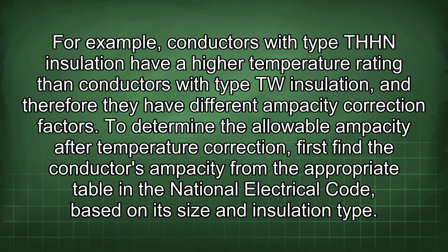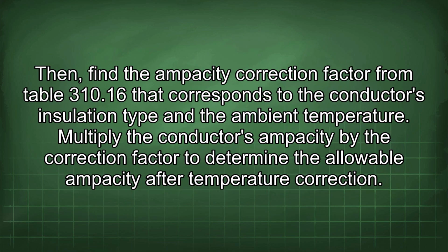To determine the allowable ampacity after temperature correction, first find the conductor's ampacity from the appropriate table in the National Electrical Code, based on its size and insulation type. Then find the ampacity correction factor from Table 310.16 that corresponds to the conductor's insulation type and the ambient temperature. Multiply the conductor's ampacity by the correction factor to determine the allowable ampacity after temperature correction.